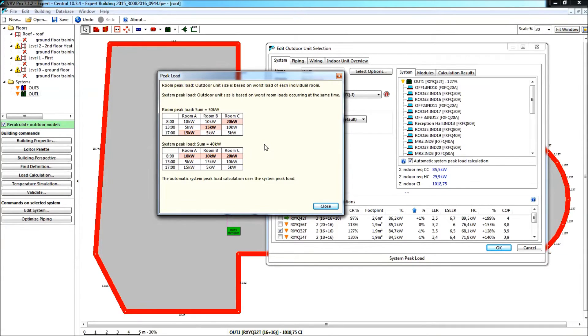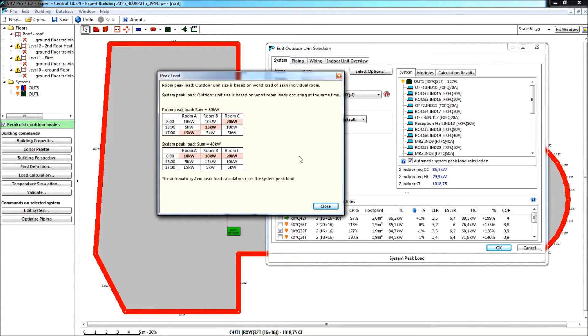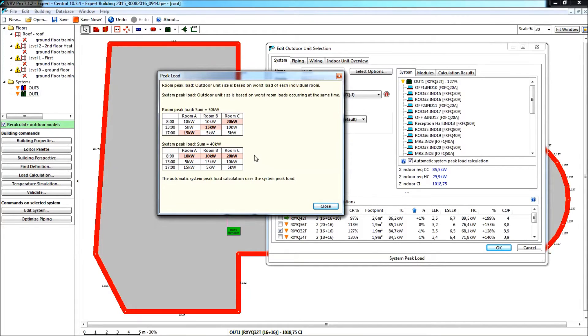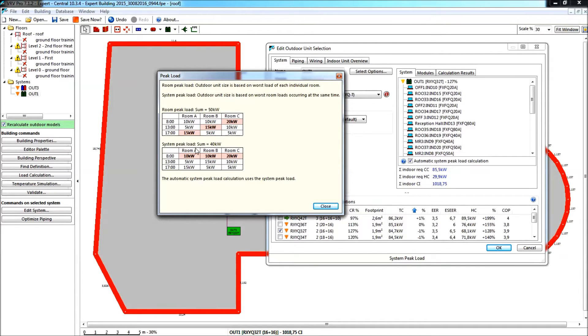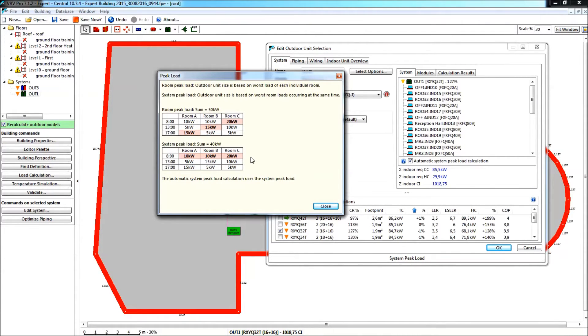Whereas, if we use the system that is ticked on by default, the automatic system peak load calculation, well, there, I will take the peak of the sum, rather, of all maximum consumptions. And here it so happens that at 8 o'clock in the morning, I have the pull down in my building there, and I see that the maximum demand during the whole day would be the sum of these peak loads here, the 10 kW, the 10 kW, and the 20 kW, so totaling 40 kW instead of 50 kW. So this is the biggest sum of units in operation, and I will size my outer unit on this biggest sum of unit that would be in operation.